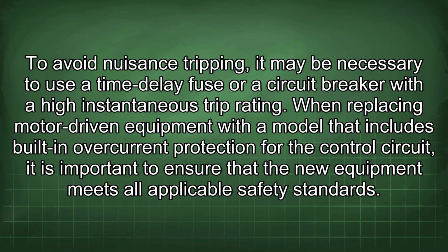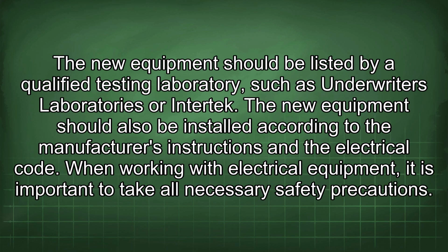When replacing motor-driven equipment with a model that includes built-in overcurrent protection for the control circuit, it is important to ensure that the new equipment meets all applicable safety standards. The new equipment should be listed by a qualified testing laboratory, such as Underwriters Laboratories or Intertek. The new equipment should also be installed according to the manufacturer's instructions and the electrical code.